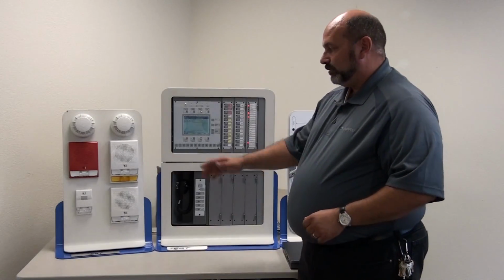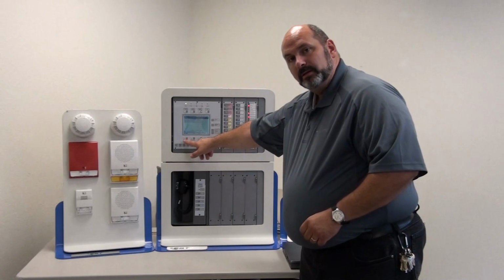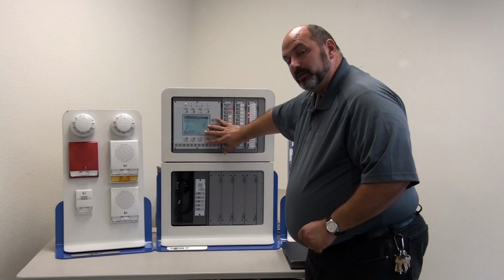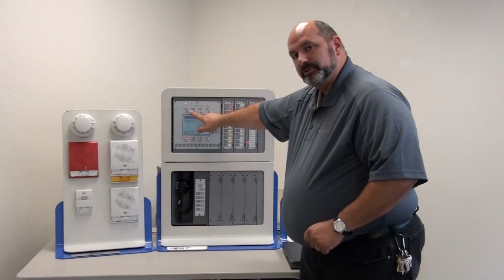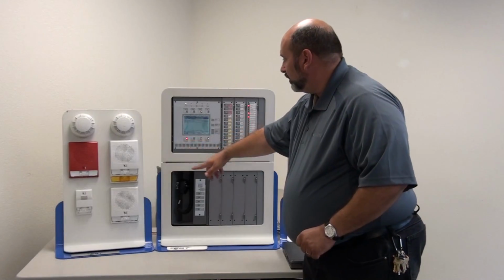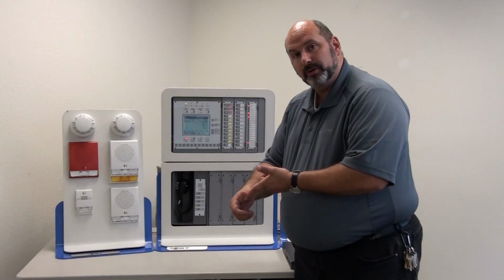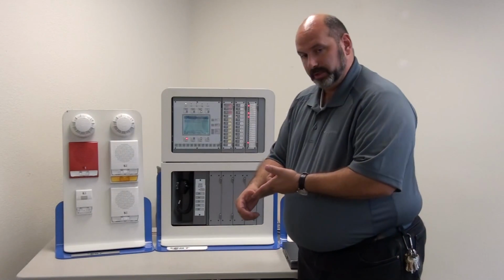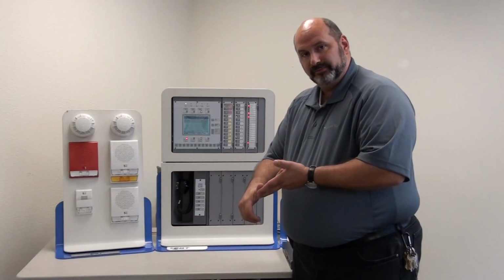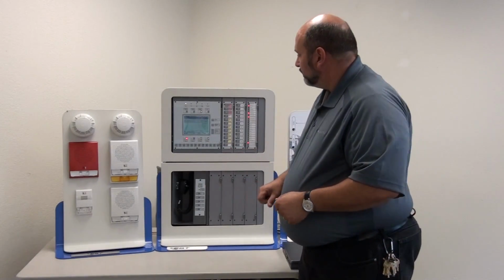Okay, so now we have horns and strobes, we have an alarm condition, a red light on the panel, and we can panel silence to make this panel quiet, but we don't want to press the alarm silence until we know for certain where that alarm is coming from and if it's an unwanted alarm or not. If somebody burned the popcorn, then we know that we can go ahead and alarm silence. If the microwave is on fire, then we'll let the fire department deal with it from there. And that's where your job is over at this point.